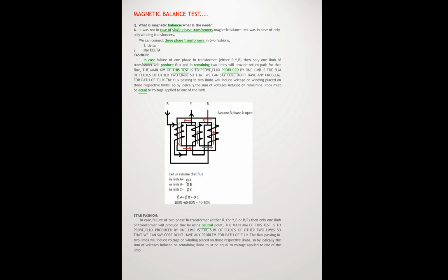diagrams. Okay, so what is magnetic balance and what is it needed for? It is not applicable in the case of a single phase transformer, and the magnetic balance test is done only for a poly-phase winding transformer, and we can connect a three phase transformer in two fashions. First is the delta winding, second is the star winding. Okay, now in case of failure of one phase in a transformer, either R, Y or B, then only one limb of the transformer will produce flux and the remaining two limbs will provide the return path for that flux. And the main aim of this test is to show that the flux produced by one limb is the sum of the fluxes in the other two limbs.